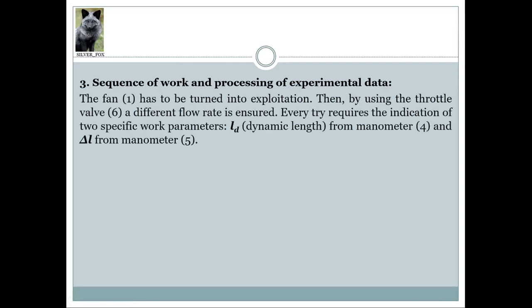Let's move on and discuss the sequence of work, data collection, and data processing. The fan must be turned into operation. Then, by using the throttle valve, different flow rates are established. Every measurement requires the indication of two work parameters: LD, the dynamic length measured by manometer 4, and ΔL measured by manometer 5.